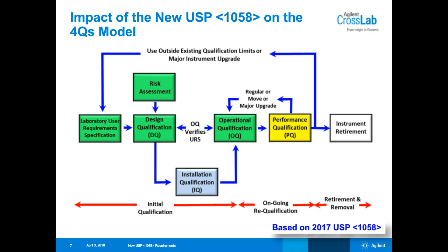Knowing the intended use and what you want to buy, you carry out a risk assessment to determine how you're going to qualify this particular instrument. The IQ takes all the pieces that you've ordered, installs them, integrates them together, and then you carry out the operational qualification, not against the design qualification, but against your laboratory user requirement specification.